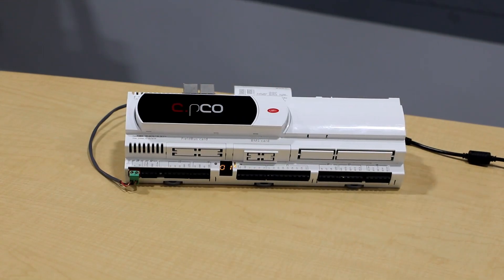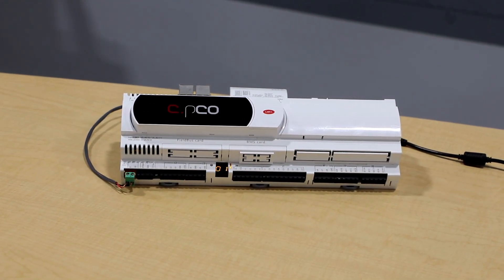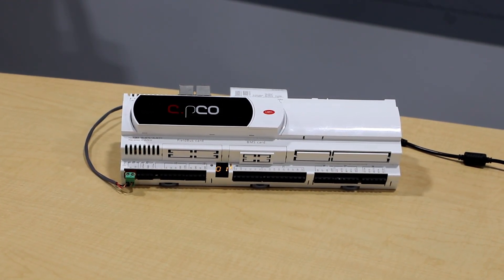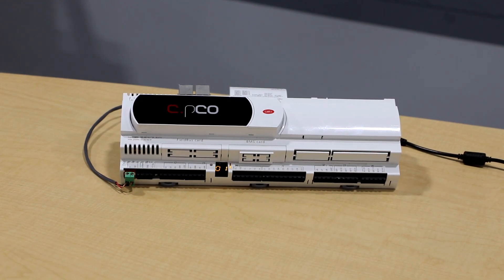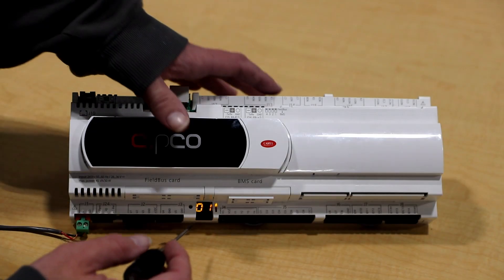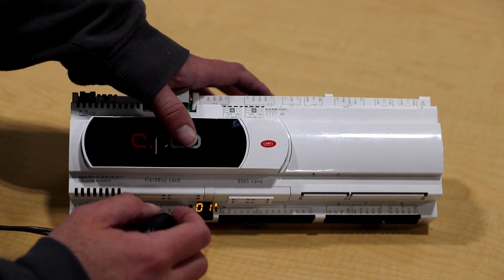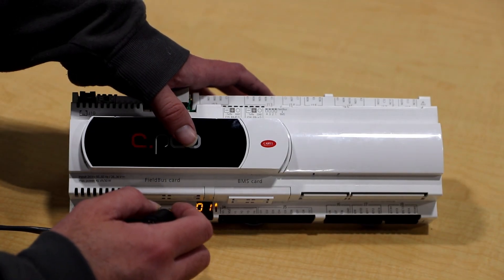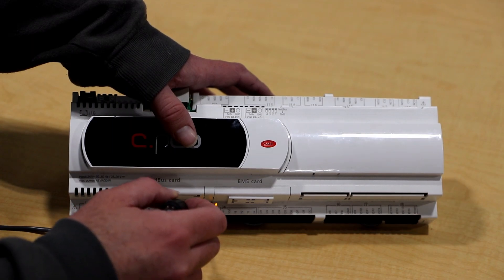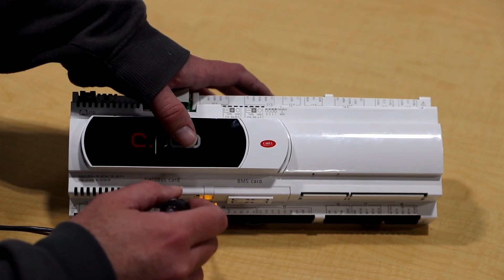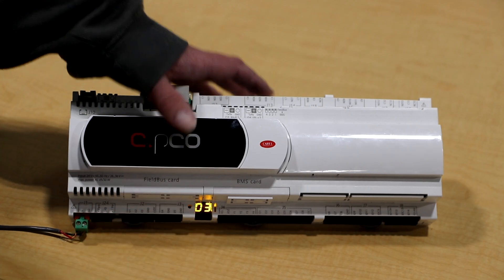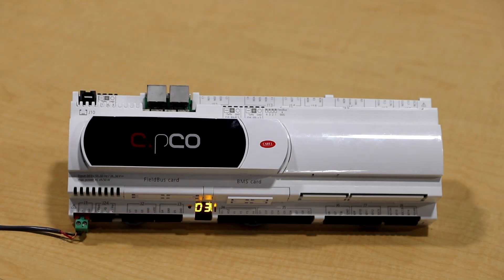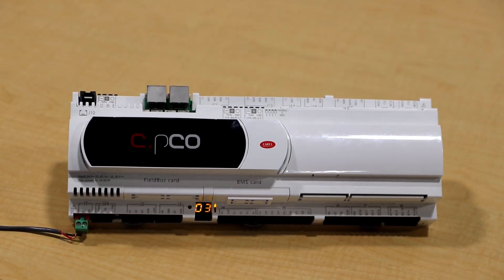To change the address of these controllers, locate the small LED screen located between J3 and J4. Place a small object such as a control screwdriver into the pinhole. Press the button until the desired address is showing. The new address should now be displayed on the LED.